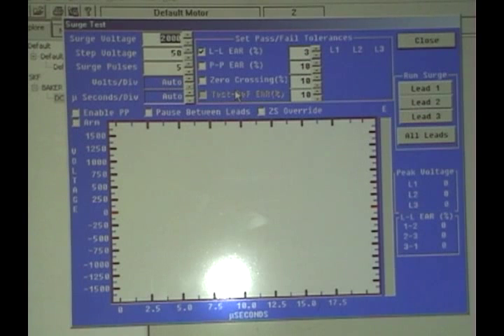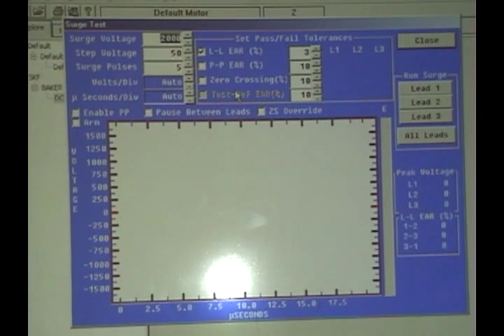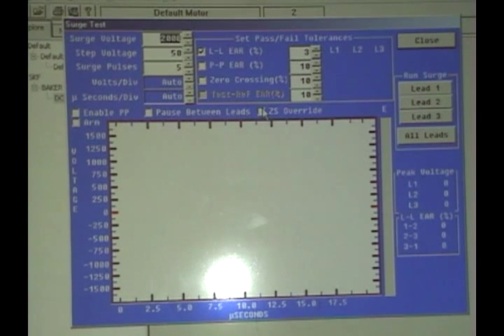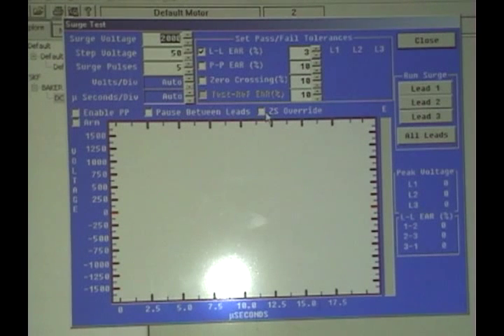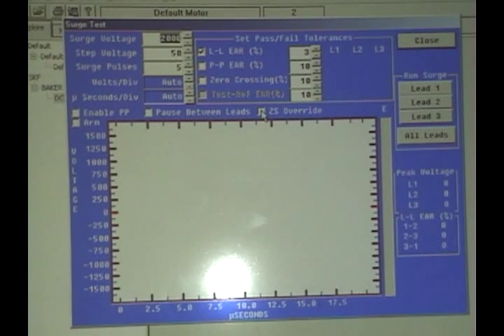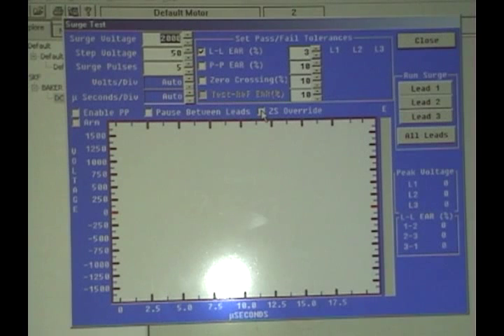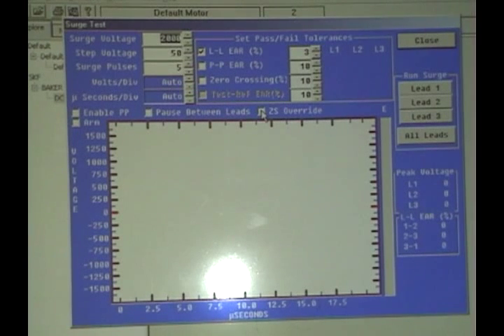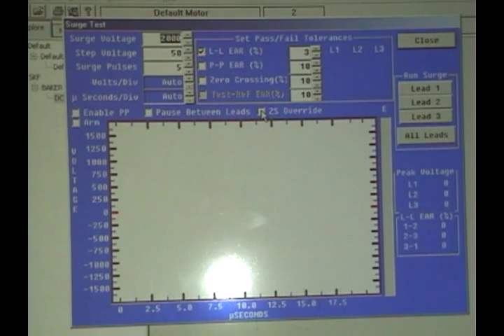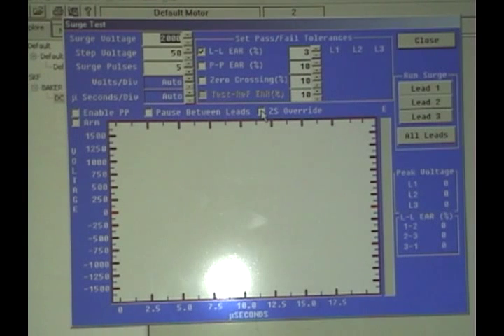Once we run the first test, we will then engage the zero start override and that will make it so that you do not have to manually ramp up the voltage every time that you want to test another series of bars on the armature.